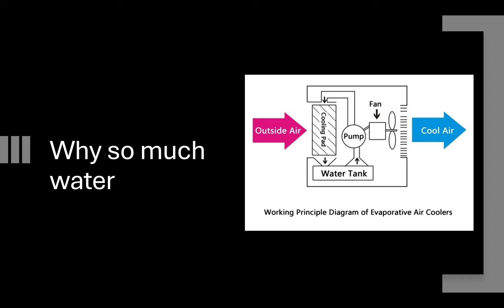Evaporative cooling, like air cooling, uses air to cool down server racks. However, it is much more energy efficient. Ambient air is passed through wet pads, and the vaporization of water in these pads consumes heat, cooling down the air passing through. This consumes less electricity than CRAC units for the same amount of cooling. Adapting pre-existing data centers to use evaporative cooling is still much cheaper than most alternative cooling methods, hence its popularity.